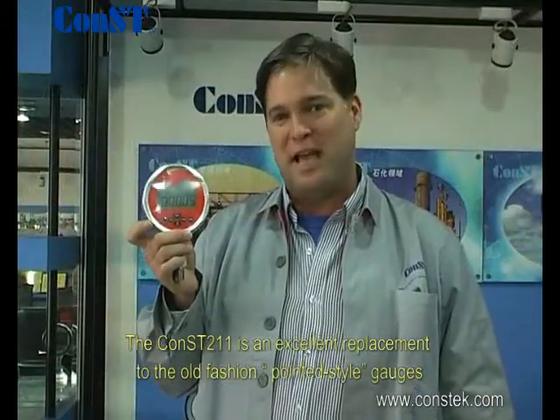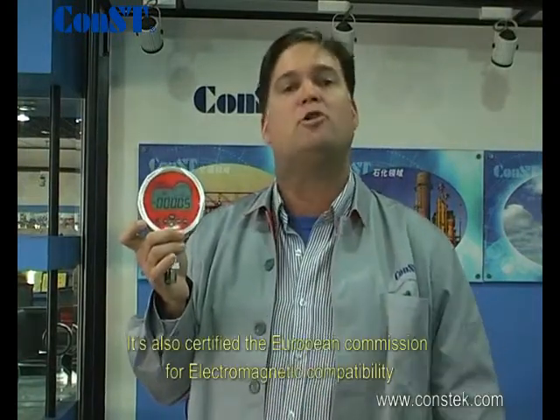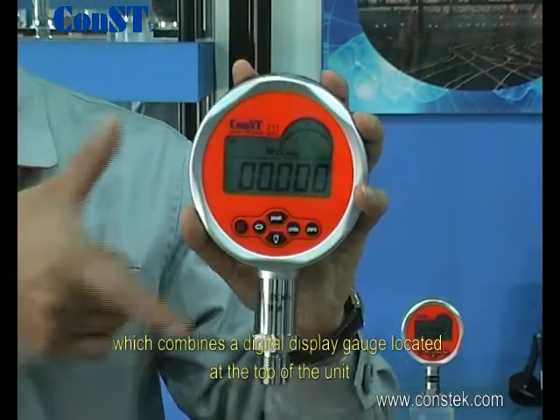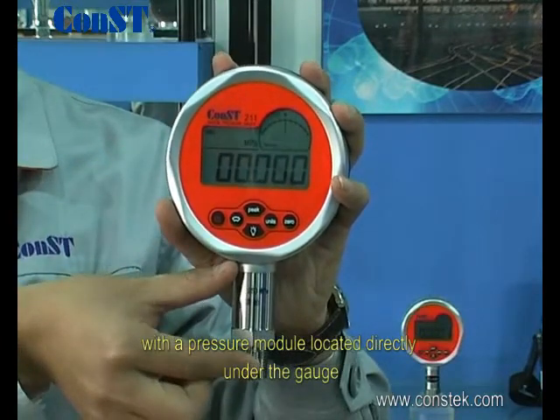The ConST211 is an excellent replacement for the old-fashioned pointed-style gauge. It's also certified by the European Commission for Electromagnetic Compatibility as well as TUV certs for Intrinsically Safe. The ConST211 has a dual design which combines a digital display gauge located at the top of the unit with a pressure module located directly under the gauge.